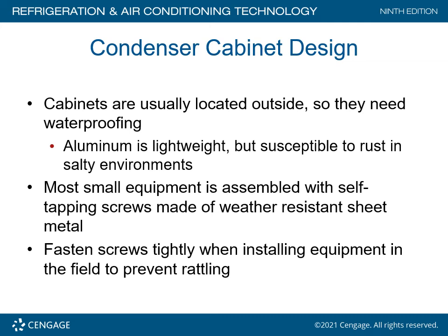Condenser cabinet design. Cabinets are usually located outside, so they need waterproofing. Aluminum is lightweight, but is susceptible to rust in salty environments. Well, I find that hard to believe. Rust in salty environments? I've never seen an aluminum coil rust. I've seen corrosion. Small equipment is assembled with self-tapping screws made of weather-resistant sheet metals.